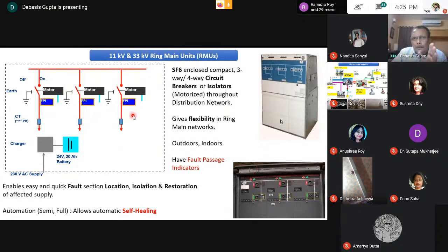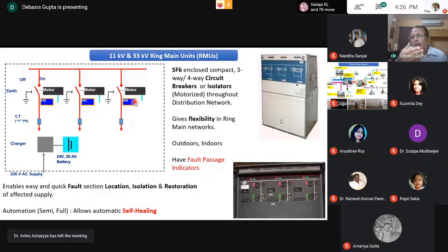Another important aspect of the RMUs is that each has an FPI, a fault passage indicator, taken from the CT, current transformer. It's an electronic device, and if the current crosses a certain value for a certain amount of time, a flag falls. This can be enabled so it's shown remotely through communicable FPIs, or engineers can go down, open the door, and check: if the FPI has worked, the fault is beyond that point; if not, the fault is before it.